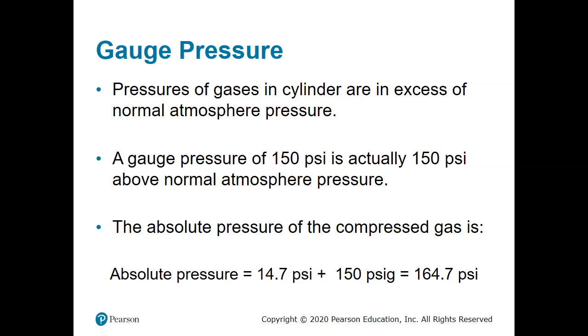This is important to note because, going back to what we were talking about at the end of Monday's lecture about the hazards associated with empty tanks, if your gauge pressure is reading 0 psi, that doesn't mean that the tank is devoid and empty of everything. What it means is that there is 1 atmosphere's worth of pressure still in there. And depending upon what that substance was, all of the hazards of that substance still apply.